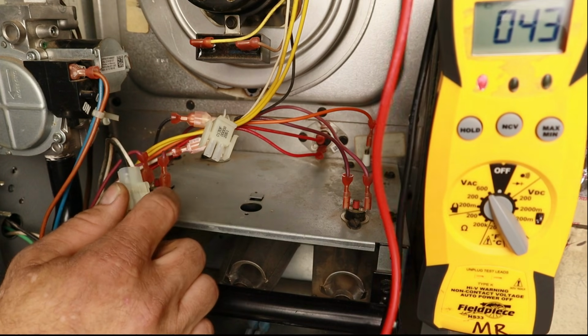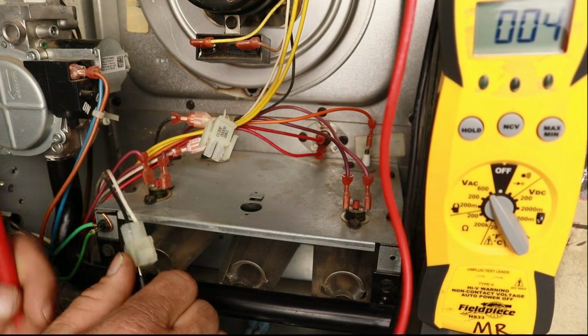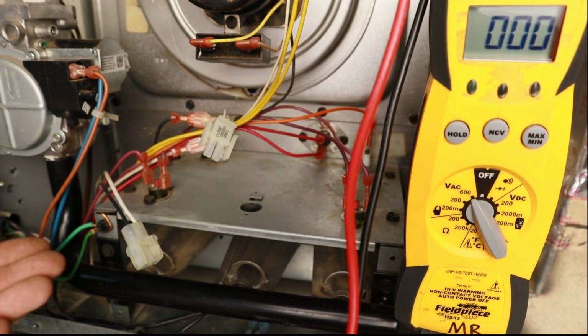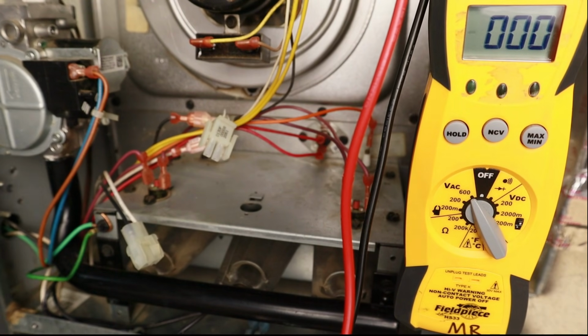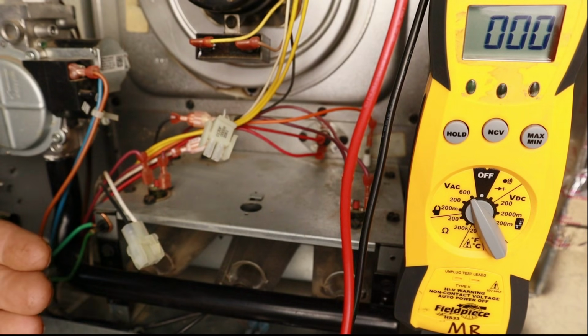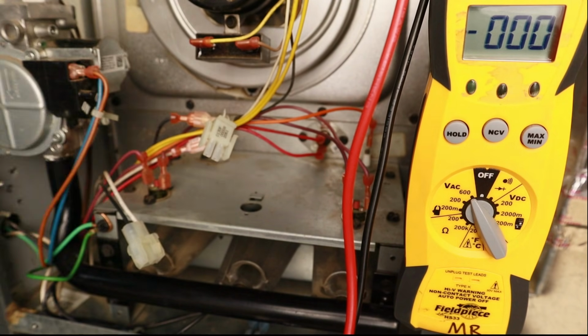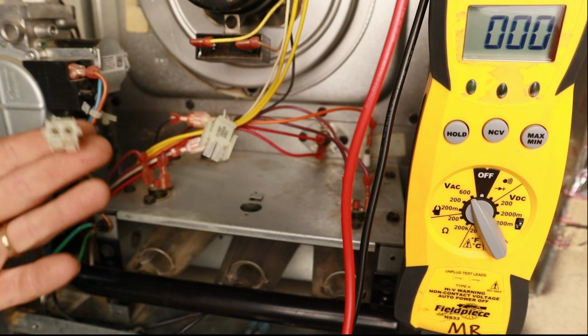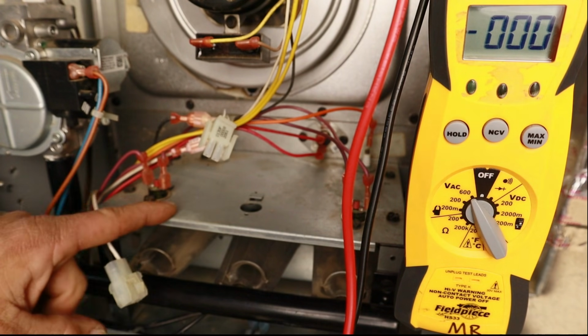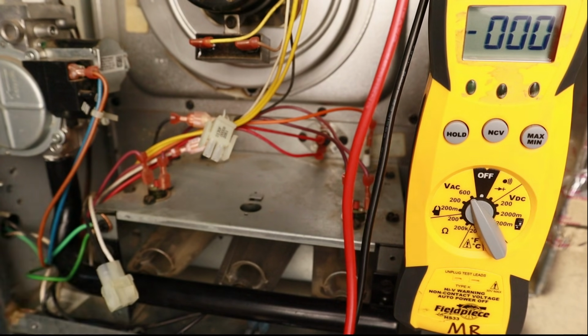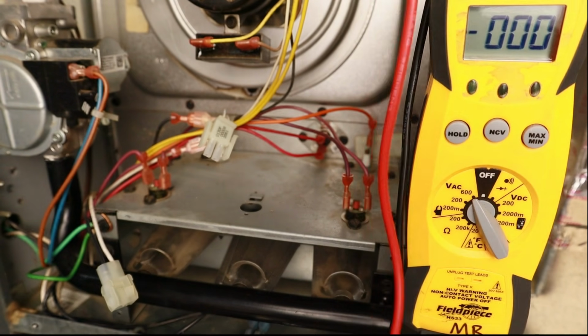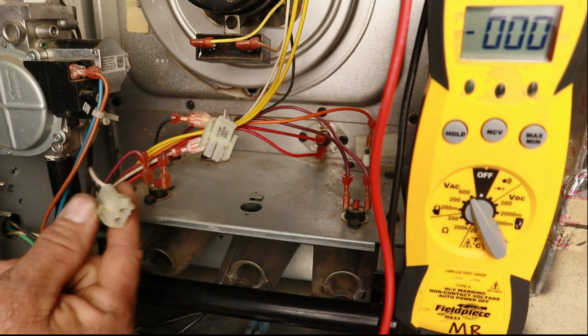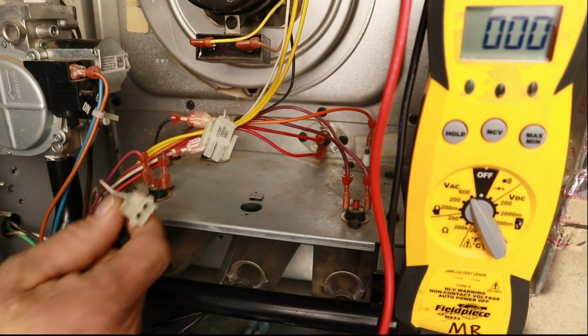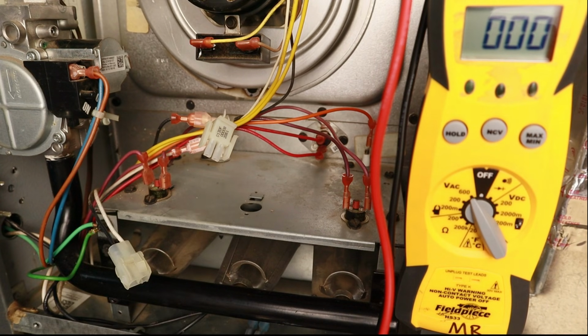Alright, so you can see now we have voltage here on our hot surface igniter. And our furnace shut down because the control board is not getting an indication that our hot surface igniter is working. So if you ever have a unit that's cycling like this and it's stopping at this point and you do have voltage here, you could end up having a bad hot surface igniter. Now obviously you could see if it's glowing or not, but if it's not glowing when it's supposed to, this is the test you can perform to see if you have any issues with the wiring, the Molex connection itself, or the control board not sending that voltage out to the hot surface igniter.